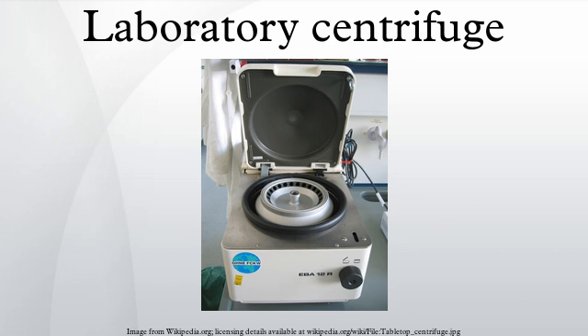The rotor can be loaded with the samples within a hood and the rotor lid fixed on the rotor. Afterwards, the aerosol-tight system of rotor and lid is transferred to the centrifuge. The rotor can then be fixed within the centrifuge without opening the lid. After the run, the entire rotor assembly, including the lid, is removed from the centrifuge to the hood for further steps, maintaining the samples within a closed system.